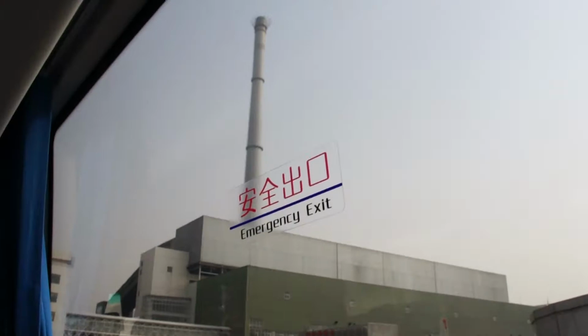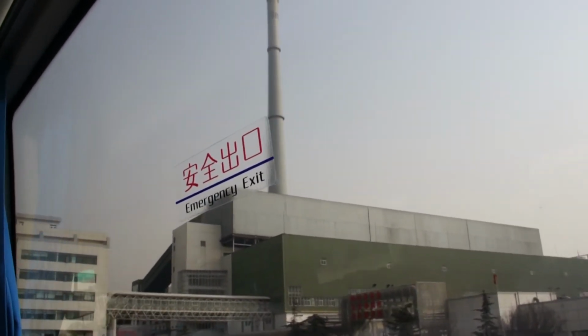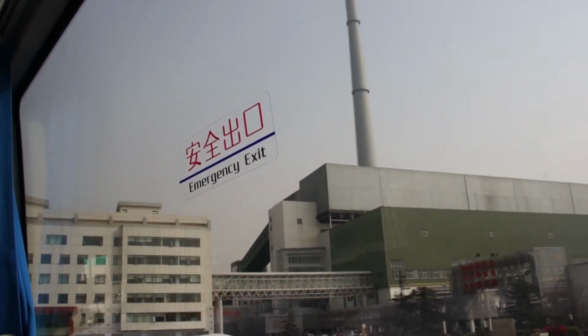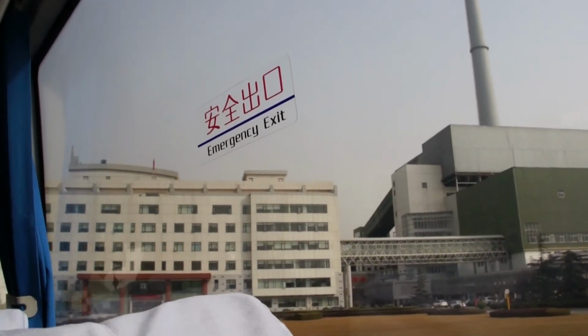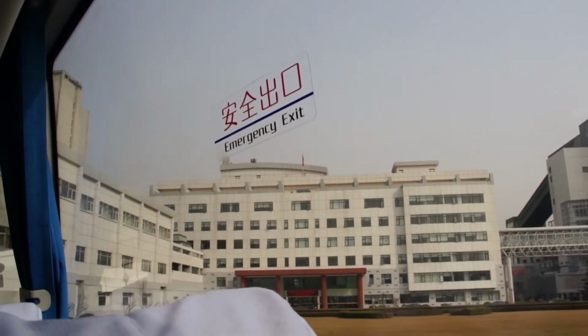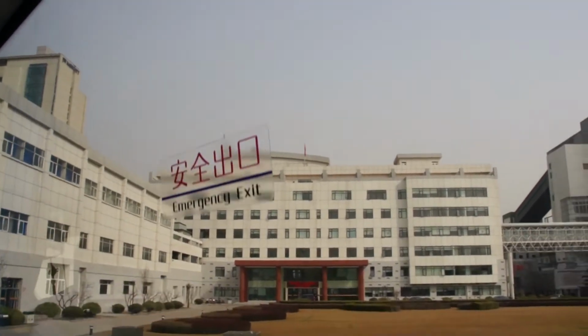You commonly hear people refer to clean coal. What clean coal usually refers to is IGCC. This plant is not IGCC. IGCC is integrated gasification combined cycle, where you take the coal and convert its state from a solid coal resource to a syngas, which is carbon monoxide and hydrogen. You can remove the carbon content prior to combustion and then combust the syngas in a gas turbine and drive a combined cycle.